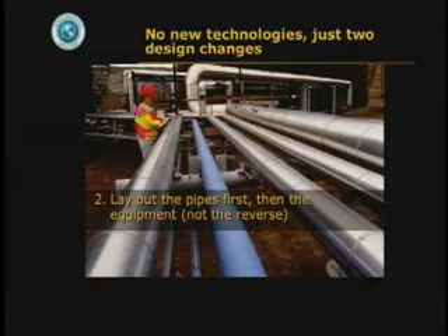Other stuff got in between. They're at the wrong height. They face the wrong way. And by the time the pipe winds its way across the space, all dressed at neat right angles like they teach us in trade school, the piping system has about 3 to 6 times the friction it should have had with a straight shot.